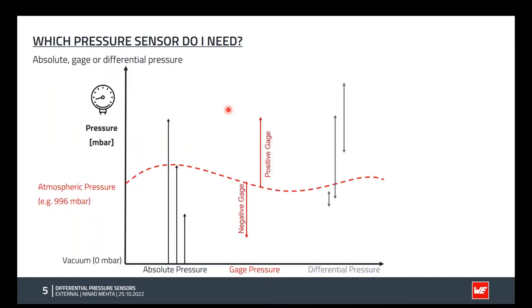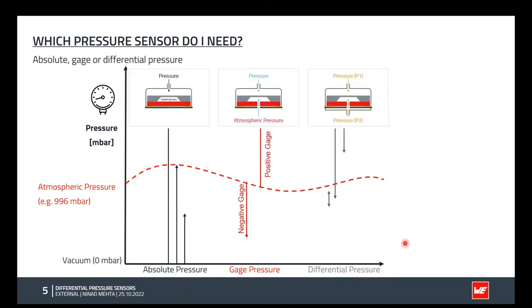Now let's go back to the previous slide where we showed different pressures, and now we can apply the piezo-resistive technology and have all three different kinds of sensor. For example, here we have in gray the piezo-resistive silicon part, which is sealed inside a vacuum so that we have a sealed vacuum during production. Then we encapsulate it, and through one outlet port, the ambient pressure can get inside. So the pressure measurement is always done against the sealed vacuum, so we have an absolute pressure sensor.